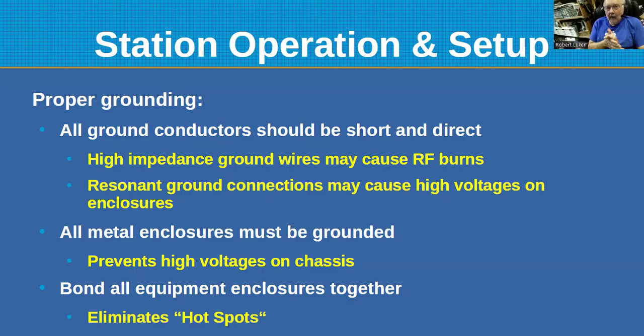And you can tie all the enclosures together, assuming that you've got them going to a single point ground. Even though they're going to a single point ground, the length of your ground wires may not all be the same, so you could still wind up with a difference in potential on the different devices because of the length of the ground wire, and there will be some inductance and resistance in that wire. So tying them together would also help equalize the potential. And that's the whole point: you want everything, particularly for lightning strikes, to be at what we call equipotential. So everything is at the same voltage and goes up and down with a lightning strike, and there's no difference in electromotive force between one device and the other, so there won't be any current flow.